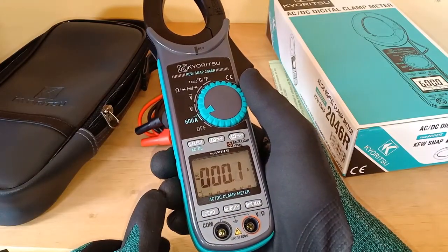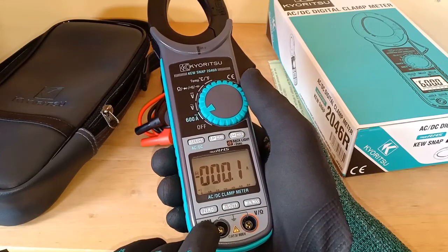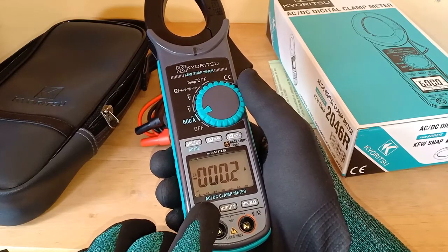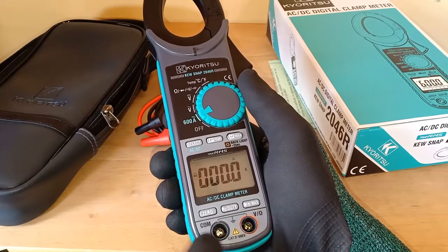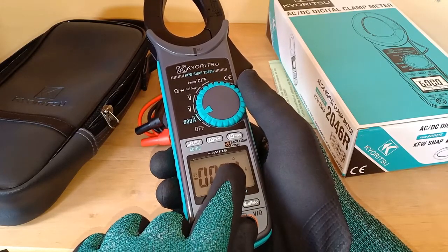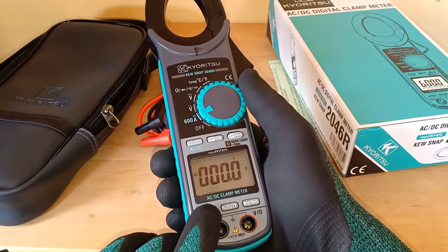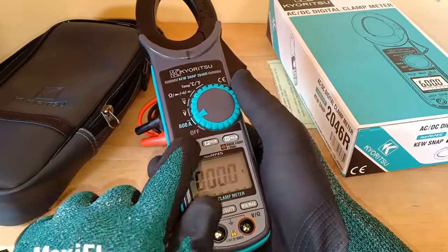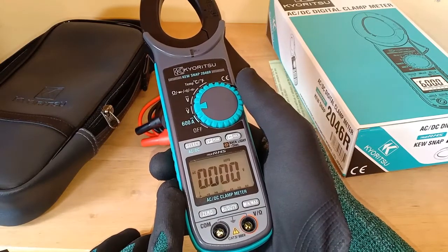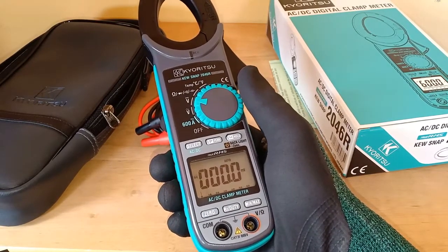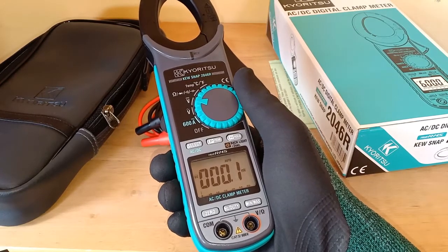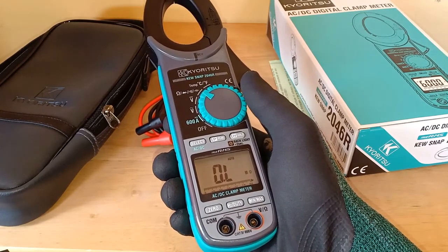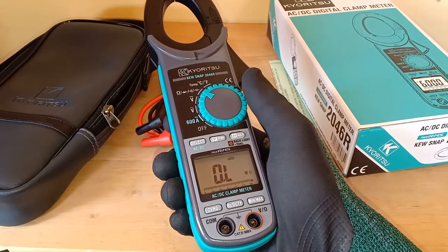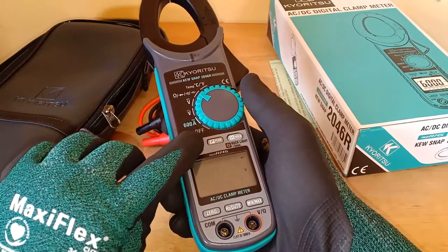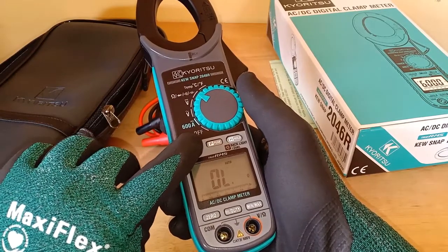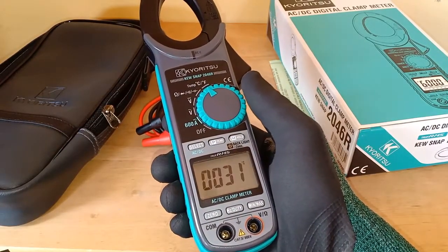For DC current measurement, the value can be reset to 0 using the 0 button, and that is indicated by the small triangle or delta sign in the display. AC voltage up to 600 volts, DC voltage up to 600 volts also, and this is the function for the resistor, diode, continuity and capacitor, which can be toggled using also the select button. And finally, the temperature function.